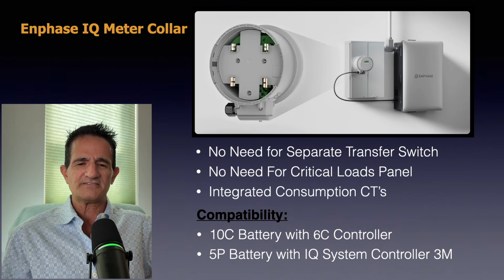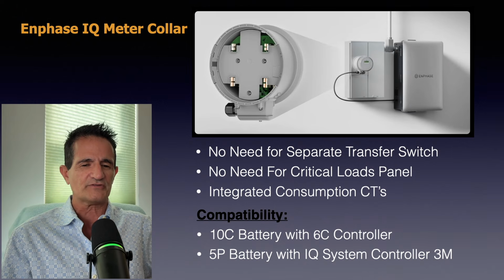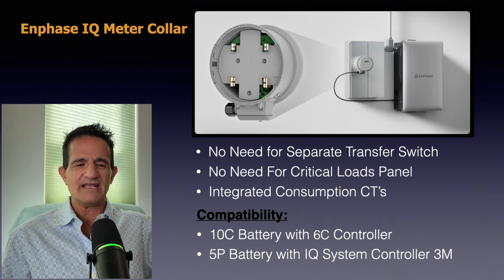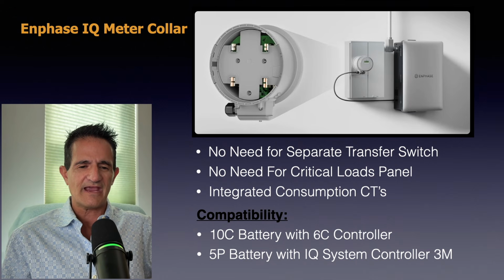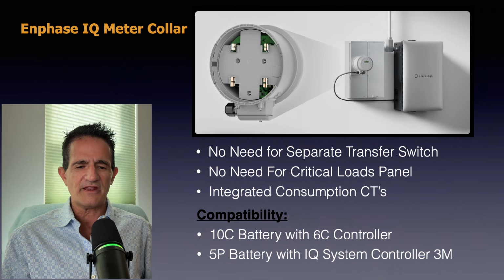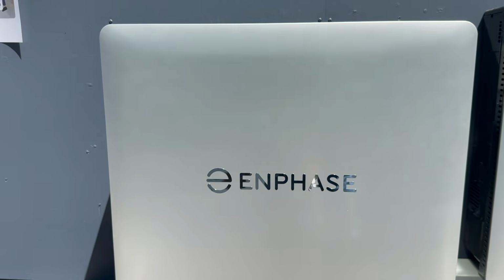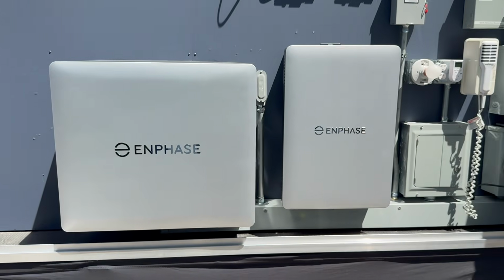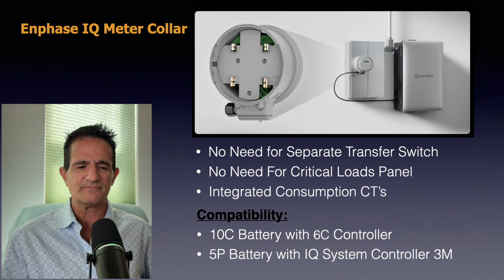The Enphase 10C does need to be used with the Enphase IQ meter collar. This is brand new. This eliminates the need for a separate transfer switch or critical loads panel, and it has integrated consumption CTs. The IQ meter collar is compatible with the 10C battery with a 6C controller, which I'll talk about in a minute. It's also compatible with a 5P battery if you use the IQ System Controller 3M.